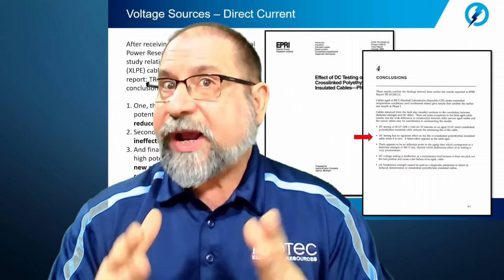So, the NETA maintenance testing specifications for shielded cables, medium and high voltage, provides options for withstand testing of cables. One of the options provided is the DC withstand test. The specification, however, clearly states that the application of DC is for extruded dielectric cables of less than 5 years in service. And it then references us to the NETA table 100.6.1. So again, key point, NETA does say that we can use the DC high potential test provided the cable has not been in service for greater than 5 years. Again, beyond 5 years, there are contaminations that get into the cable, and DC will have a negative effect on these.